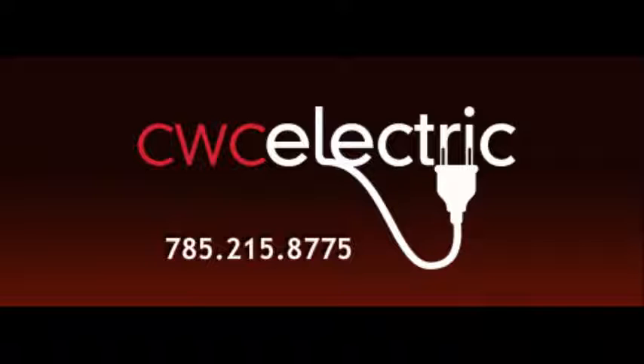But to make a comparison, most people are familiar with Volkswagen, how they falsified test results to show their cars were getting better emission standards in order to sell. Federal Pacific did the exact same thing back in the 70s and 80s. They falsified laboratory results that showed that their circuit breakers worked properly when, in fact, they knew they didn't. And so they lost their UL, or Underwriters Laboratories, listing. They have about a 30 to 40% failure rate. And when I say failure, I mean they will not trip when they should. People say, the one that never trips, it always works. Well, that's what they're famous for. Electricians will call them welder panels, because you can sit there and overload something and they will rarely trip.